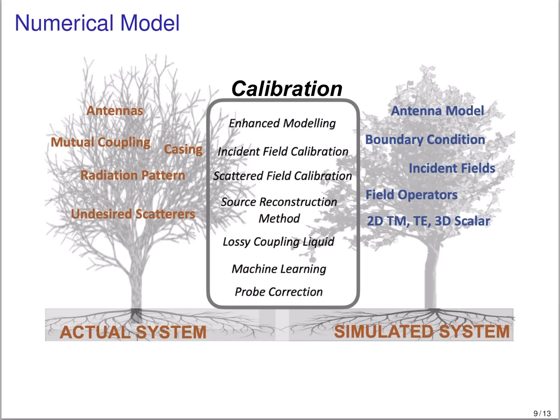The last component governing the success of nonlinear inversion is how close the simulated or numerical model is to the actual system. In the actual system we deal with antennas and mutual coupling, while the simulated system may not incorporate effects such as mutual coupling, casings, etc. There are different ways to establish this connection: enhanced modeling, scattered field calibration — where you compare measured scattered data from a known target with simulated data to construct calibration coefficients — use of a lossy coupling liquid to minimize reflections from the casing, and other techniques such as machine learning, probe correction, and source reconstruction methods.